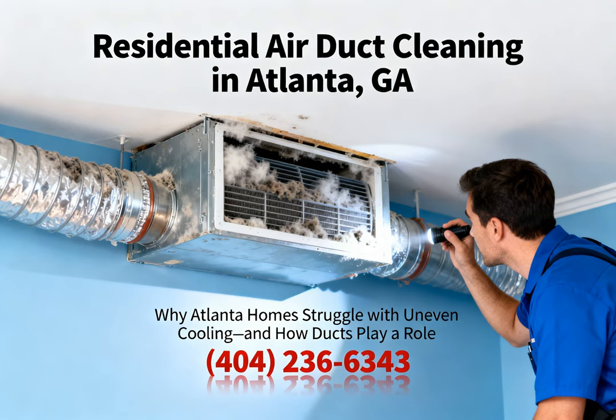That is a brilliant analogy, and it is the exact reason why proper HVAC maintenance requires certified specialists, not just guesswork. So you can't just DIY it. No, you really cannot just jam a high MERV filter into an older system. Before any advanced filtration is installed, a technician must perform a static pressure test. A static pressure test. So they are measuring the actual aerodynamic force inside the system.